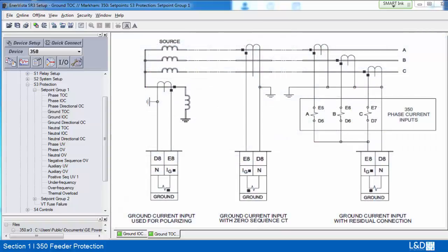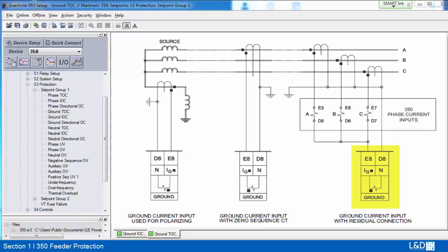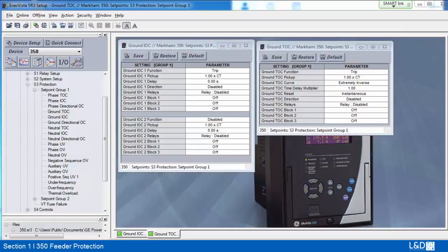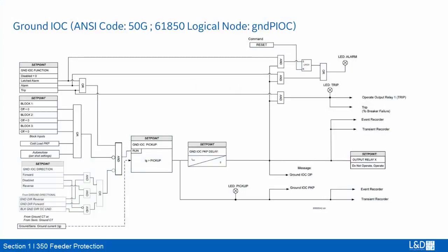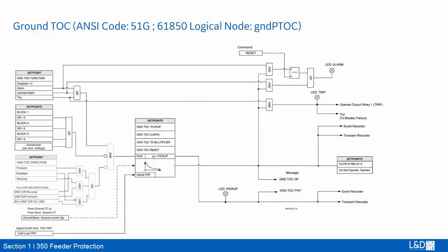There are three ways to get the ground current: by neutral grounding CT, zero-sequence CT, and residual connection. The settings are the same as phase IOC and TOC. From the logic diagram, the input current is from IG or sensitive ground input. It has blocking from digital inputs: autoreclose and directional.